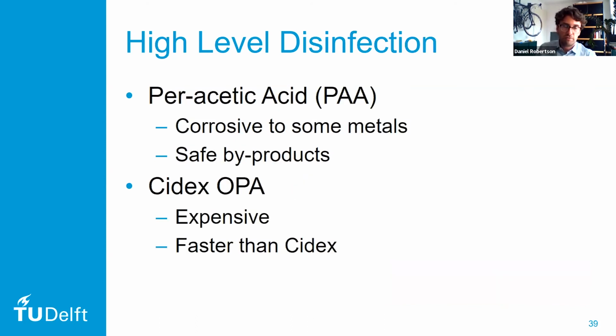Now, some other options for high-level disinfectants that are around are, for instance, peracetic acid, which is an acid-based disinfectant. This peracetic acid generally has safe byproducts, so it's not toxic to use, and it's quite fast. The only problem is that it's corrosive to some metals. So especially if you use disposable instruments, it can be corrosive to some of the materials that are on your surgical instruments. And the other one is Cidex OPA. The advantage is that it's faster than Cidex. The disadvantage is that it's much more expensive. So again, there are advantages and disadvantages to all of the disinfectants.